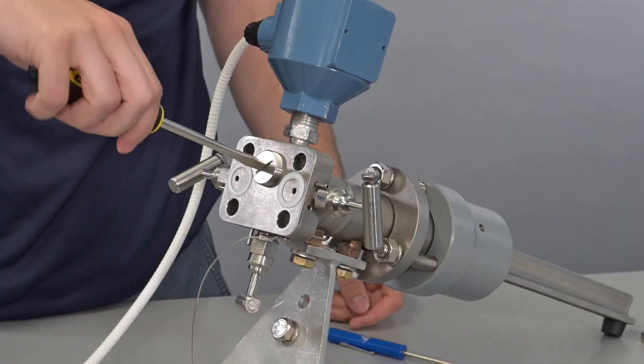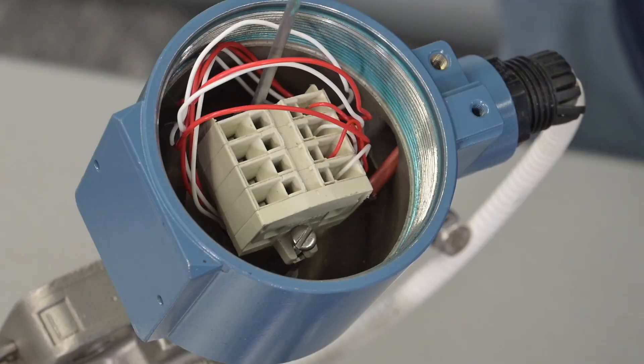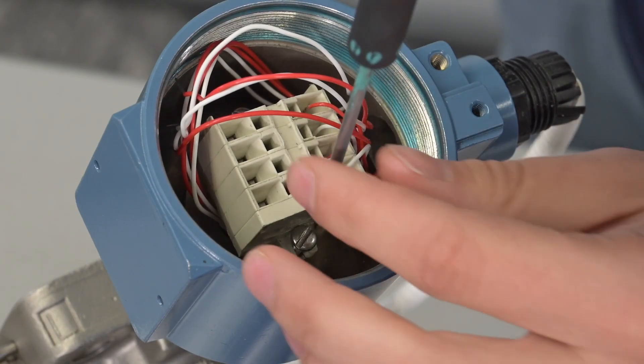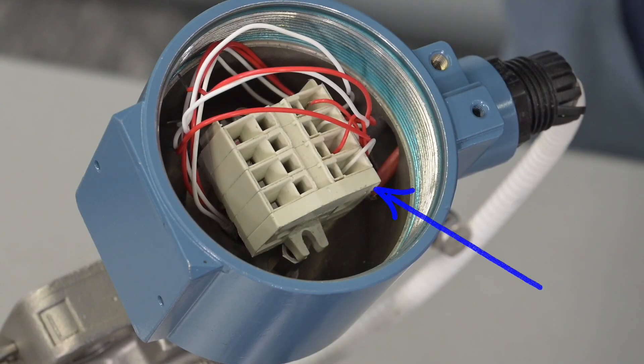Using a large screwdriver, remove the plug from the Annubar to expose the RTD wires. Remove the terminal block from the RTD housing by unscrewing the two connection screws. Make sure you keep the wires on the one side of the terminal block connected.